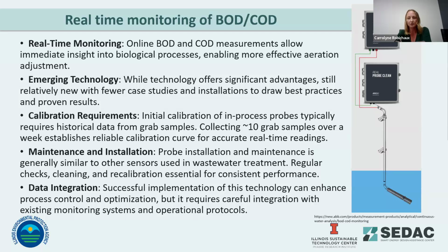This one is showing you actually the air blast cleaner that's going to go down to the sensor face. So as Sean mentioned, these are not reportable probes. They are correlation to measurement. They are pretty accurate. You just need to create a site-specific correlation curve. Obviously, all of you know that this is against a 5-day test or a 3-hour test, depending upon measurement.